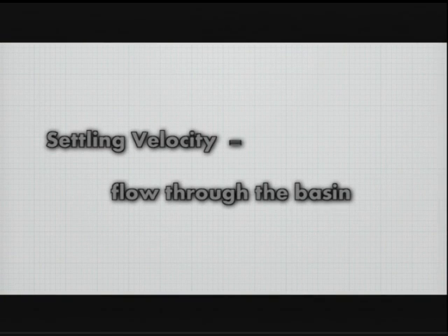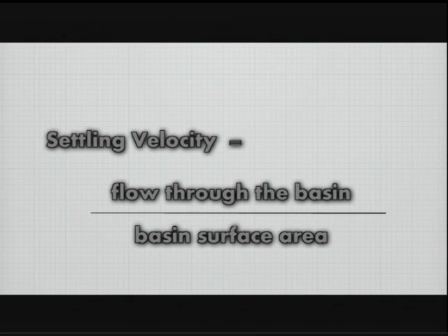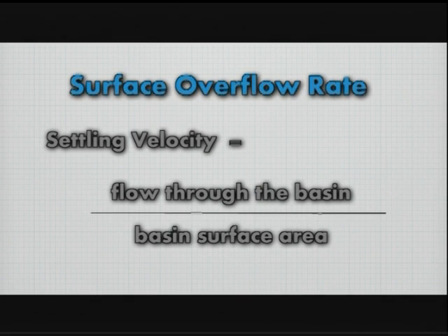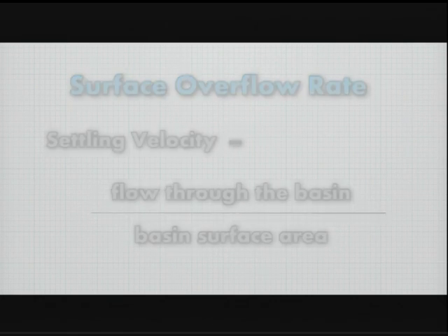The settling velocity is determined by the flow through the basin divided by the basin surface area, or surface overflow rate. Notice that the depth of the sedimentation tank or clarifier is not a consideration in the calculation of surface overflow rate. Overflow rates depend on settling velocity of the flow, or are equal to the settling velocity of the smallest, lightest particles being removed.